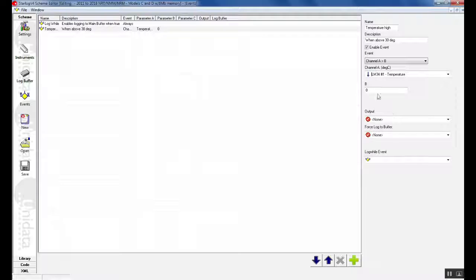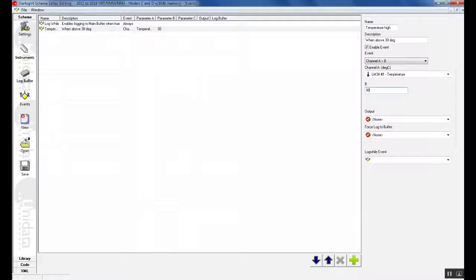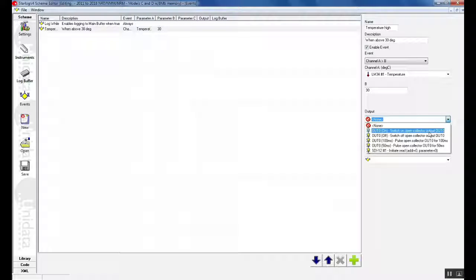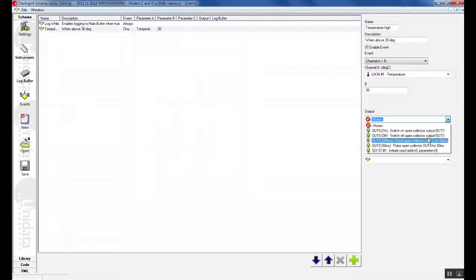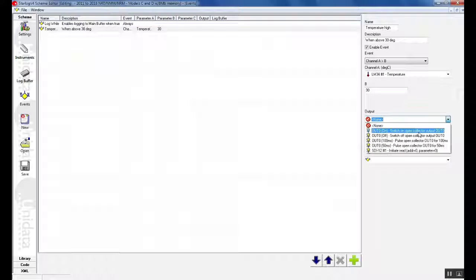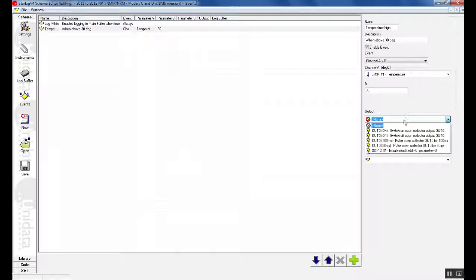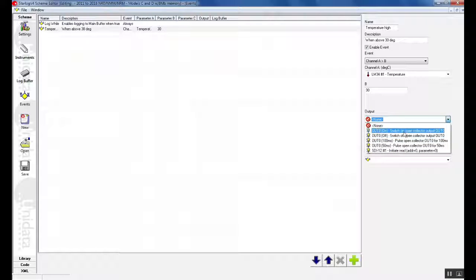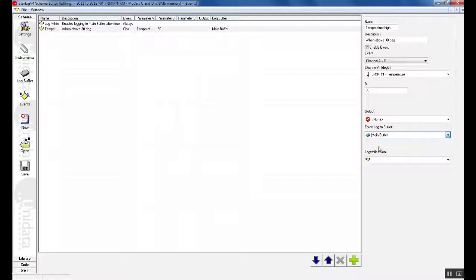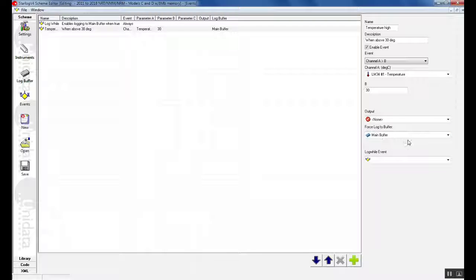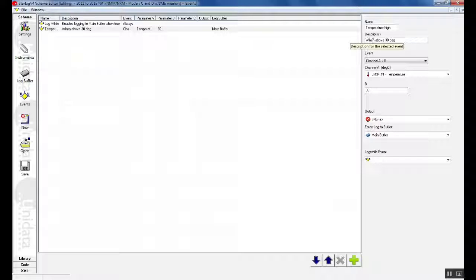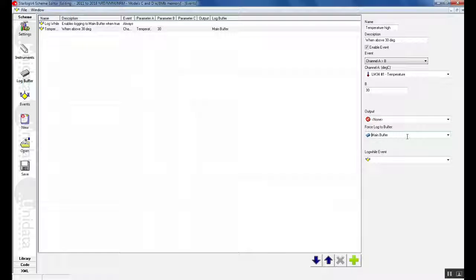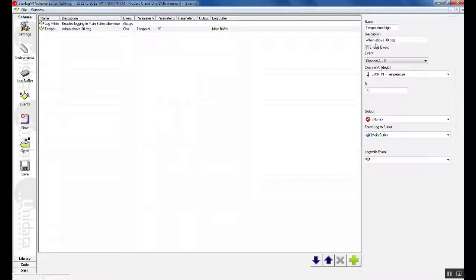We select our temperature channel and then we type in the value that we would like to trigger. So 30 degrees on our temperature channel. We have outputs on the NRT so we can trigger an open collector output. For example if we wanted to turn on a light or a siren or we can initiate a read. Anything you would like here you can do. For this one we will not select anything. In this section we will select that we would like to force the log to main buffer. This indicates that when the temperature will go above 30 degrees then the NRT will start logging every 10 seconds according to the scan rate instead of logging every 5 minutes. Once this event is not true anymore then the logging will go back to its 5 minute point.